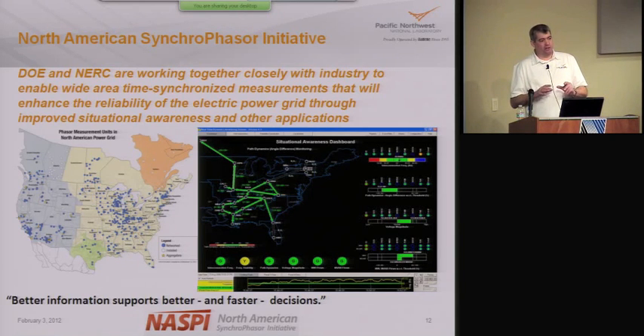One great example was during a hurricane event, where a utility in Louisiana had transmission lines separate or open, splitting part of their grid into a different island. They had two islands within their operating territory running in parallel with each other. Having PMU information allowed them to better assess the situation and reconnect lines to bring that island back into synchronism with the rest of their system, without having to shut the island down and then reconnect transmission lines and bring generation back up. They estimate this dramatically saved restoration time through better measurements.